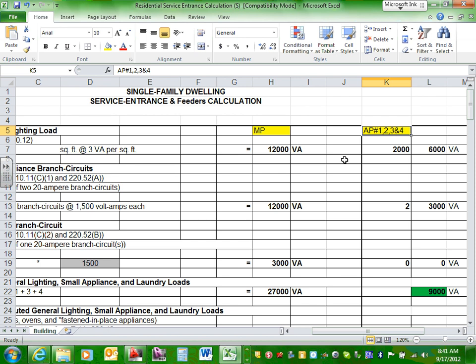We have four apartments. Now, do you guys think we're going to do a calculation for each one of them? That's one way. The engineering way is you really want to end up with one apartment 110 amps, another apartment 100 amp. Does it sound good? So what we do, guys, in a situation like this is we take the largest apartment. Can I have thumbs up? The largest square foot apartment. And we apply this one to all the other apartments. Why? Because we're not going to be splitting hair here.